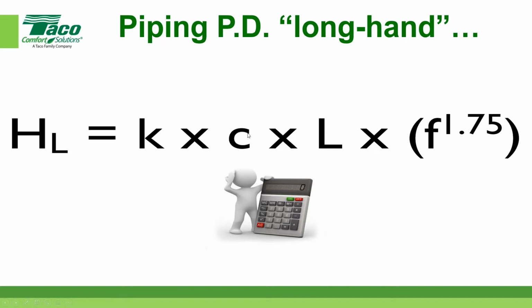So that's my correction factors. Again, that's a number, and we'll times that by the total developed length. This is assuming that you've already given an equivalency to the straight pipe as well as the fittings and valves and all that stuff. And then finally, you times it by the flow, which is what the F stands for, the flow to the power of 1.75.